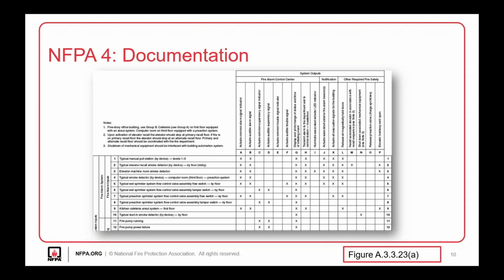creating the documentation. So as the input-output matrix is something that's created by the system designer, it's important that this input-output matrix be correct. So once the integrated testing agent receives this documentation from the registered design professional, they should review it and confirm that it's correct. And if it's not correct, they need to return it to that registered design professional in order for them to correct it for any issues. So as fire protection engineers, you may be the registered design professional for some of these integrated systems. Because of that, you need to make sure that your matrix and/or your narrative include all the correct interactions with the integrated systems that are integrated with the system that you're designing.